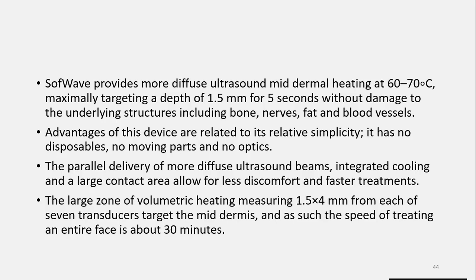Large zones of volumetric heating measuring 1.5 by 4 millimeter from each of the 7 transducers target the mid-dermis, and as such, the speed of treating the entire face is about 30 minutes. So in 30 minutes, you can deliver a complete treatment for the face.